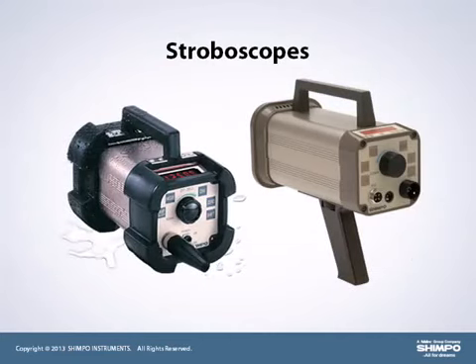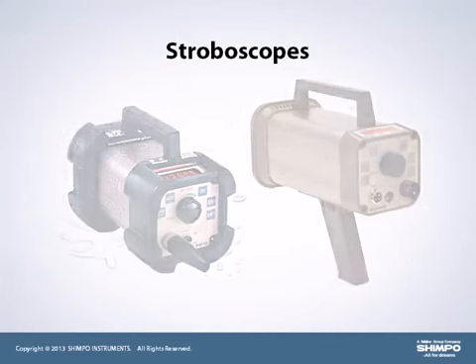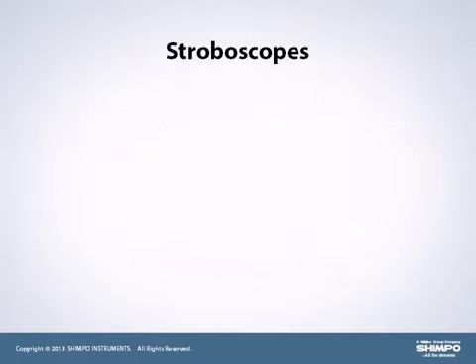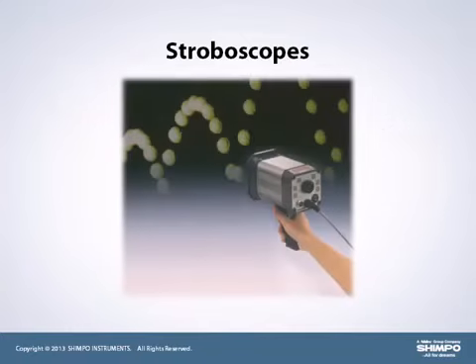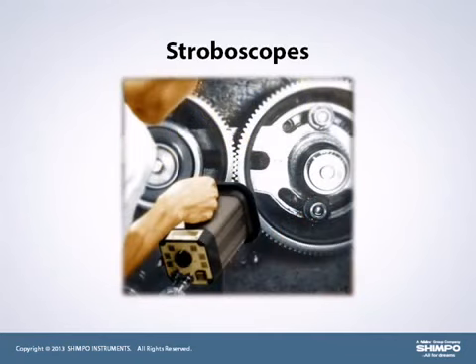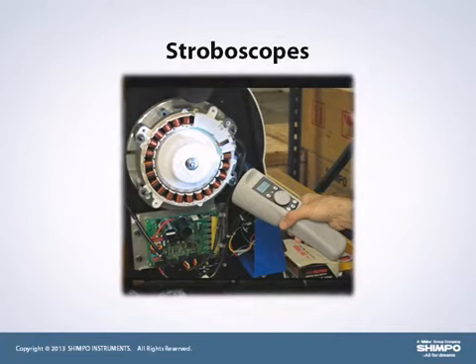Stroboscopes are motion analyzing devices that are adjusted to flash at various rates. Technicians who oversee the operation of equipment such as compressors, pumps, fans, any motor driven machinery, or system with repetitive motion has the potential to greatly benefit from the use of a stroboscope.